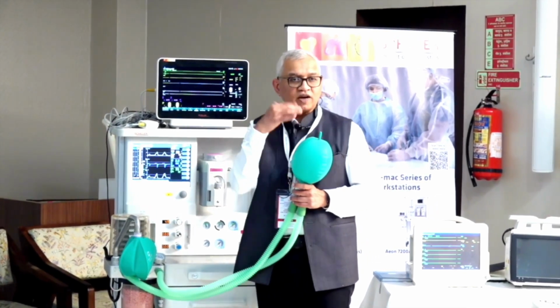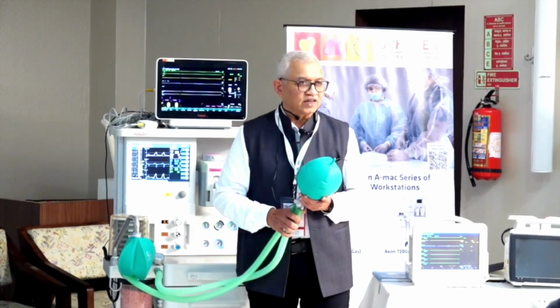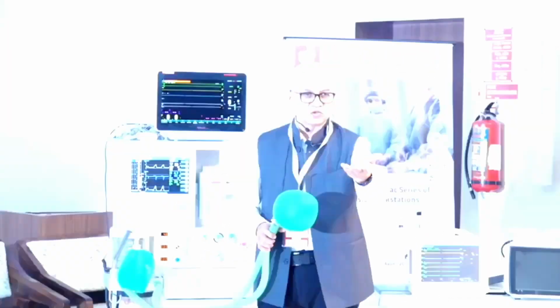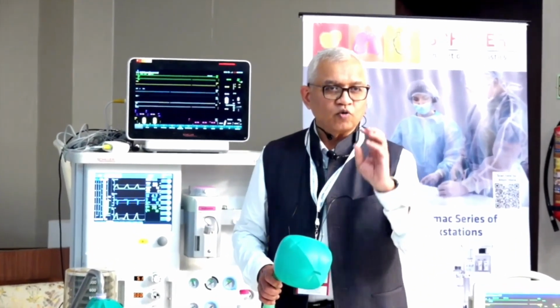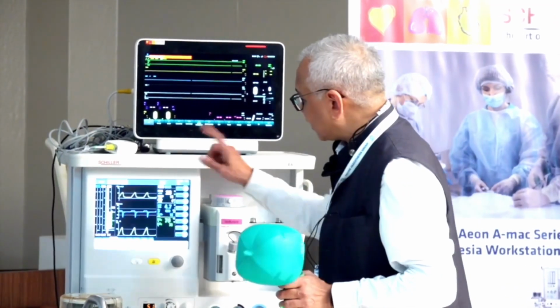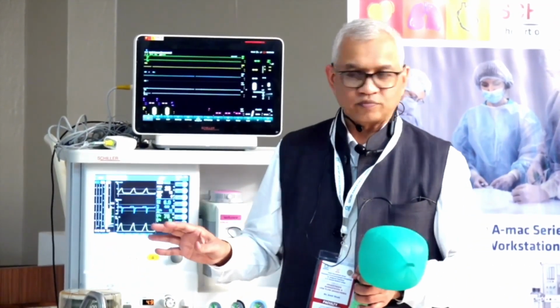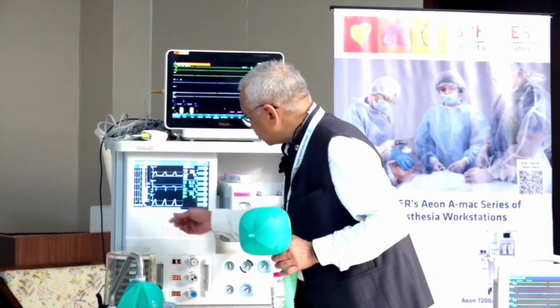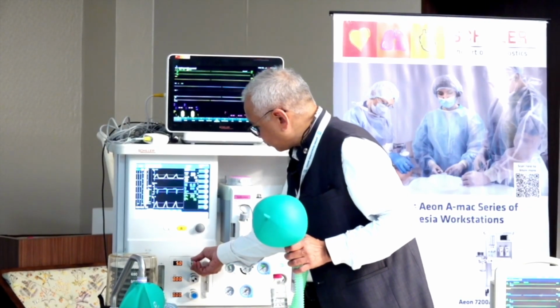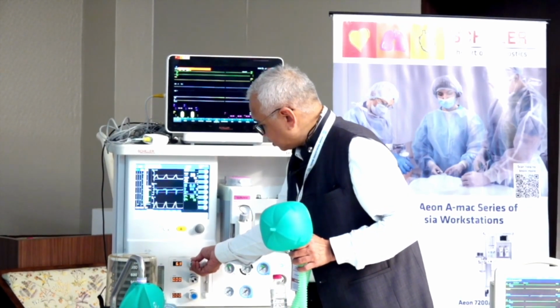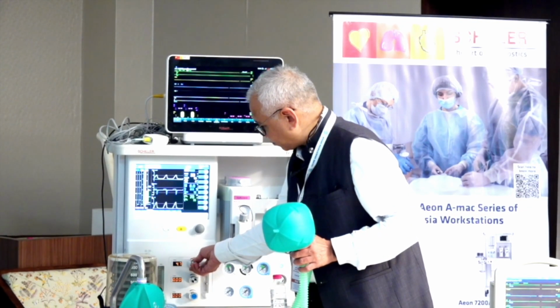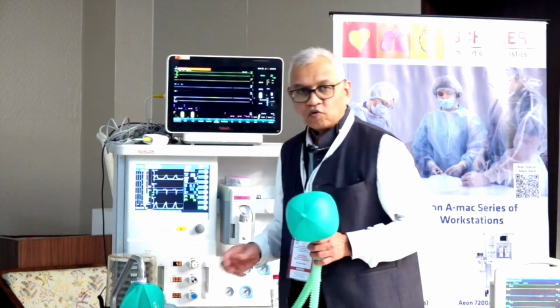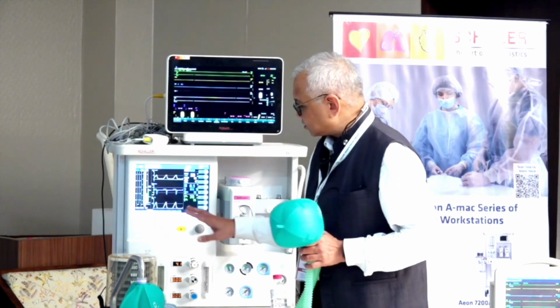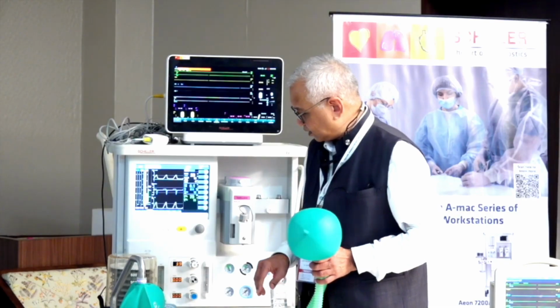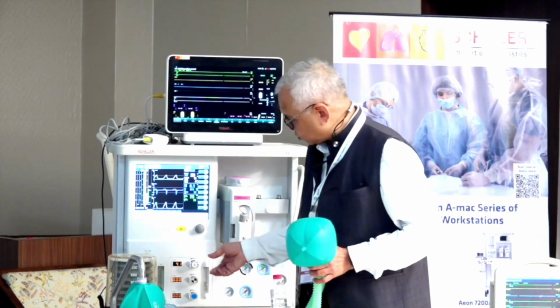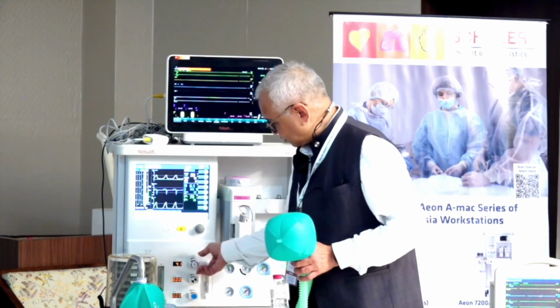Now to quantify the leak, suppose you do not have tests and you want to know exactly how much leak it is because you want to use low flow. You can gradually go down on the flow. So what you do is reduce the flow. Sorry. Keep it at 4. Okay. It is still achieving the full height. It is not going down. So the leak is less than 4 liter.